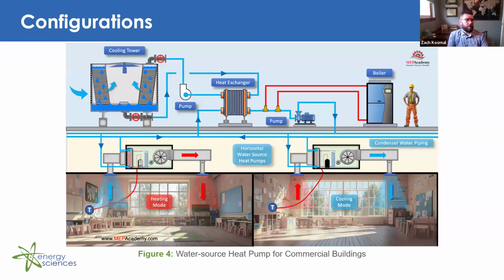Moving on, so this is an example of a water source heat pump in which a cooling tower and a boiler are utilized for supplemental heating and cooling. So I didn't mention this previously, but with water source heat pumps, you can tie in a cooling tower or a chiller and a boiler to do that supplemental heating and cooling when needed. So this setup, it allows for different zones in a building to simultaneously heat and cool. With the water loop, you can see the water loop is just below that roof level, the horizontal blue piping. That's acting as your thermal exchange medium. So if a space is calling for heating, it'll pull heat from a space that may be calling for cooling, and it can distribute that heat to the area that's requiring that heat. So the boiler and chiller or cooling tower in this case are like the system's backup dancers, if you will. They step in only when the internal heat exchange between zones isn't enough to keep the loop in balance.